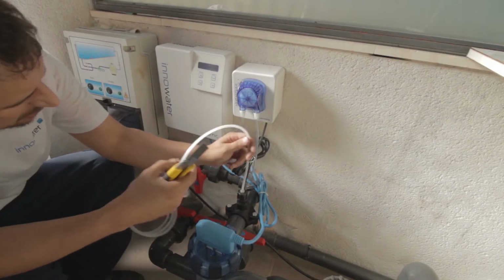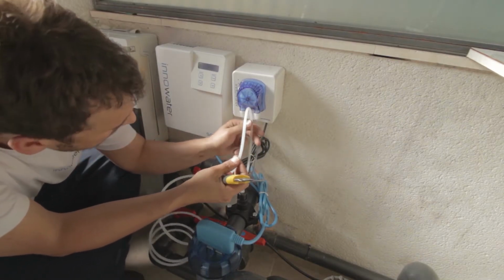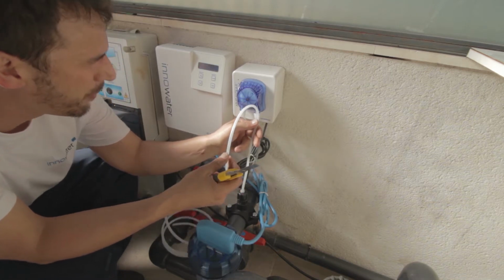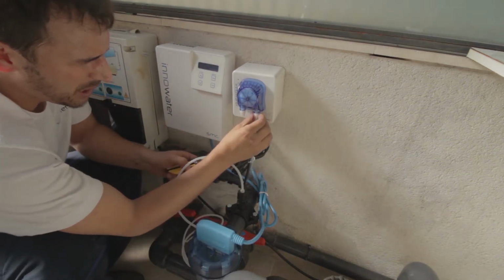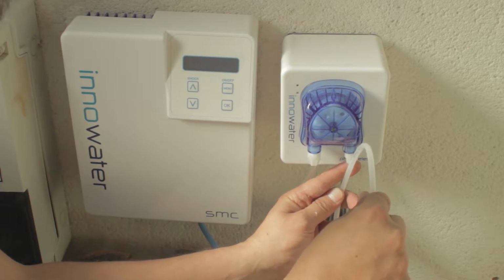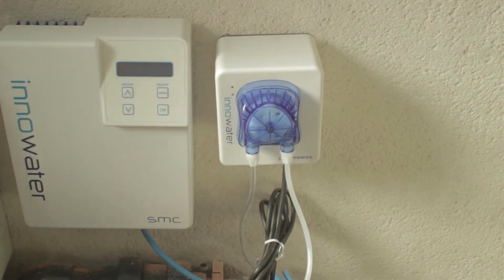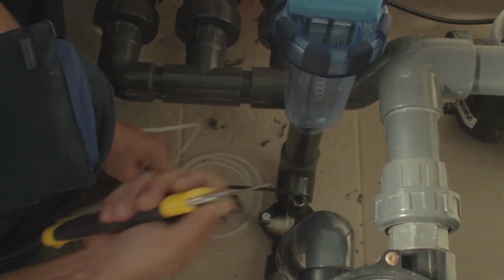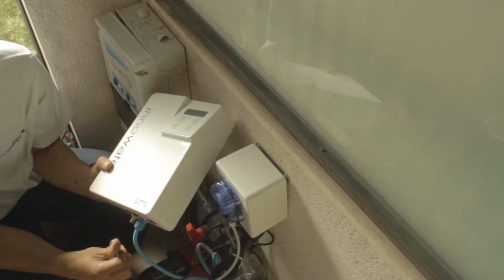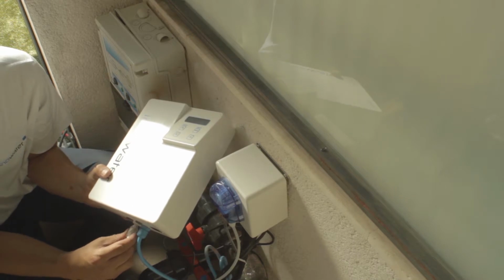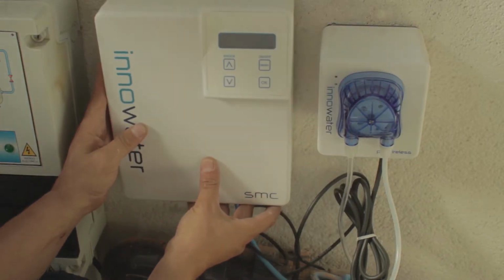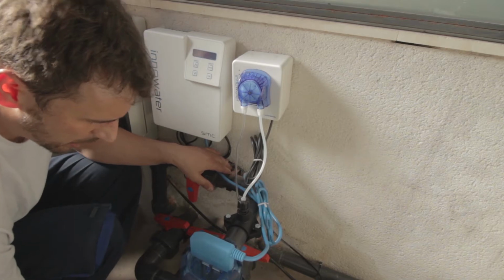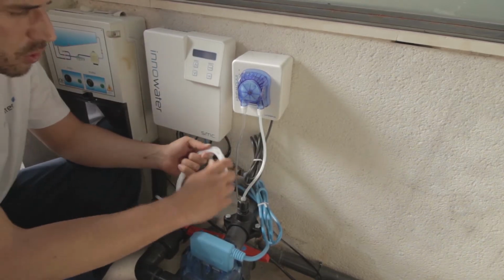How to connect the acid pipes in the regulator. The pressure pipe is fitted into pump exit on the right hand side. Remove the sample tube and join it as tightly as possible to the connection, screwing it on firmly and ensuring that the tube is not loose. Keep the leftover tubing in case of replacement.